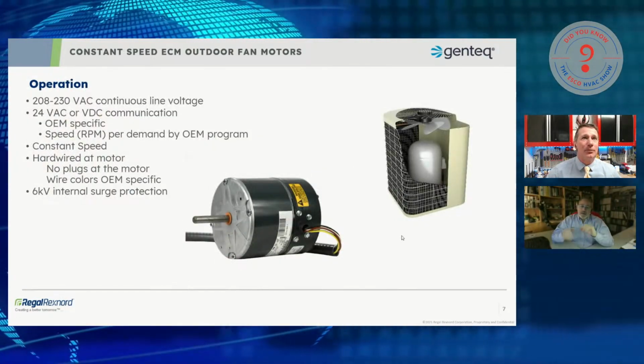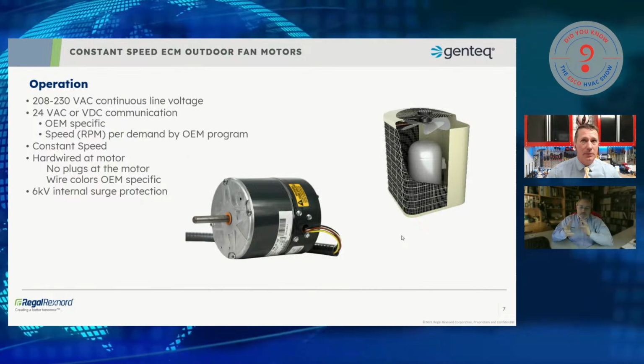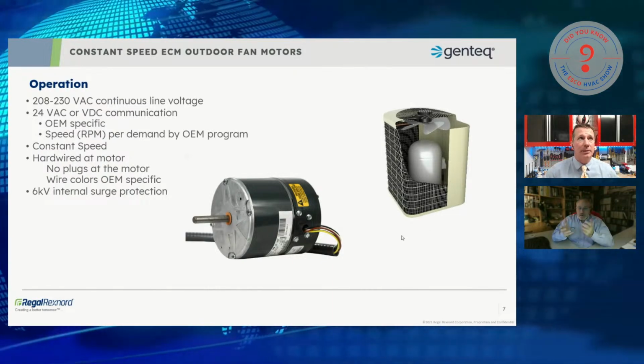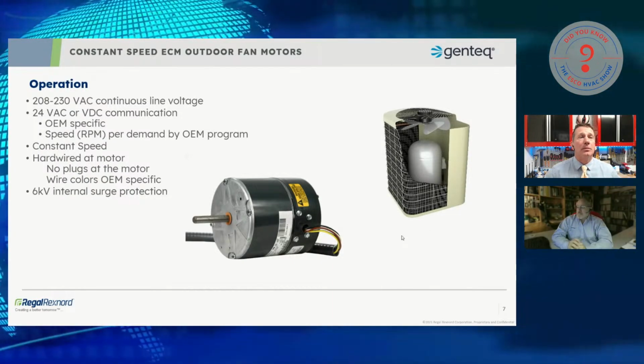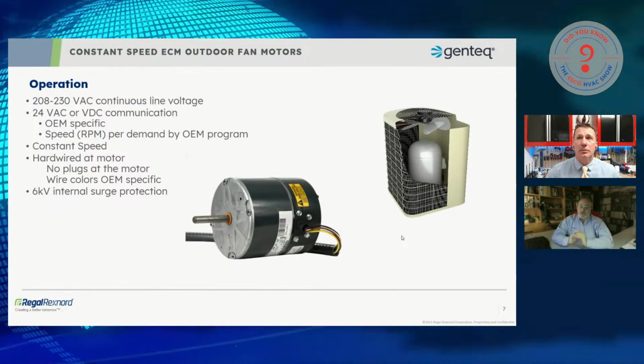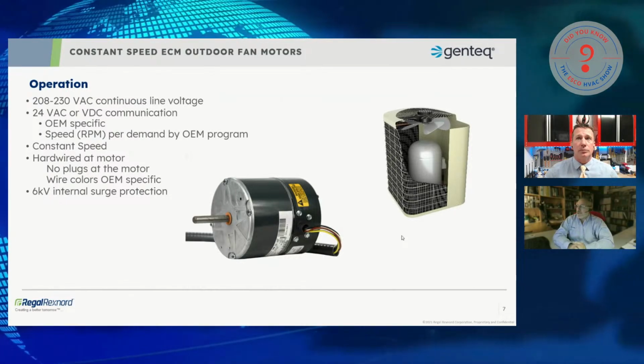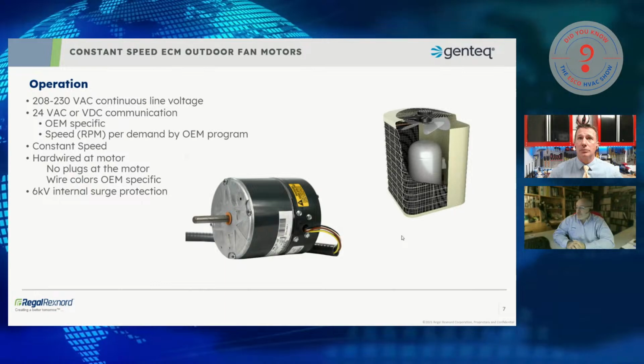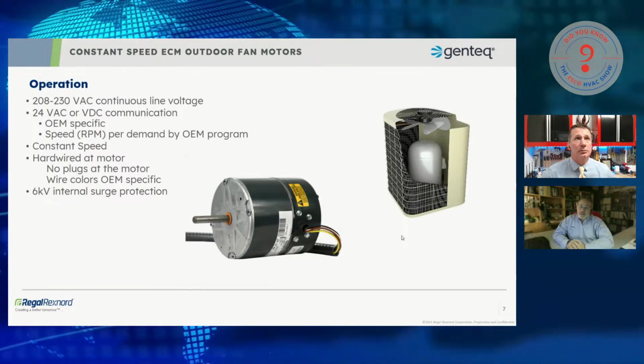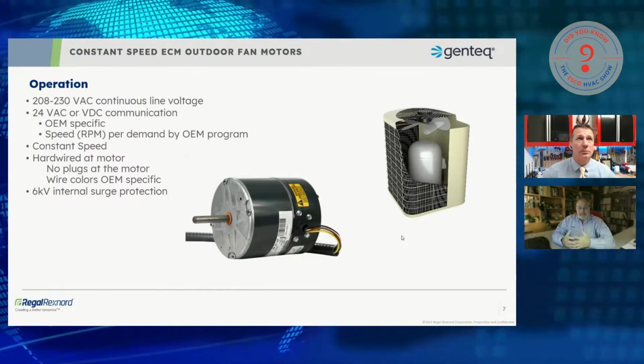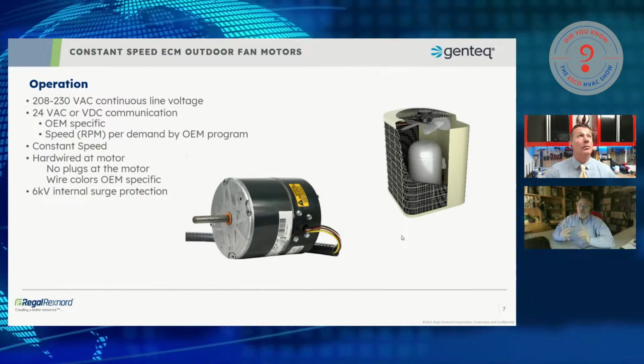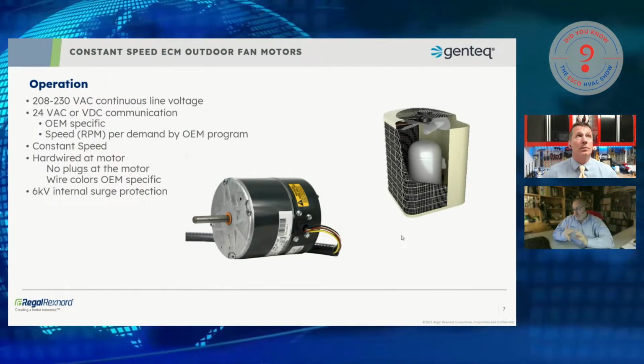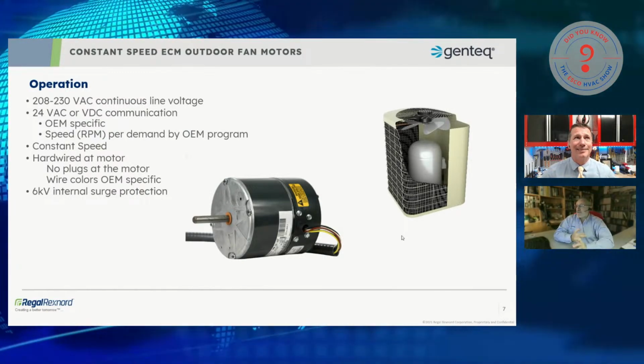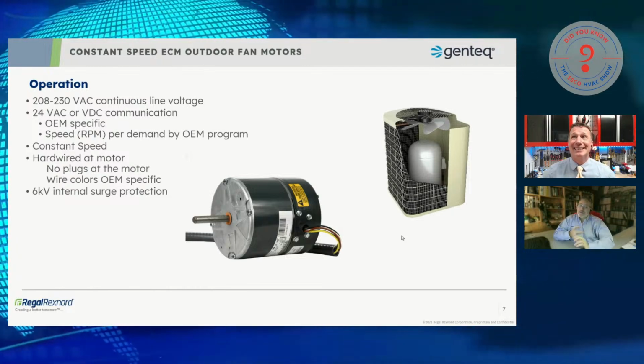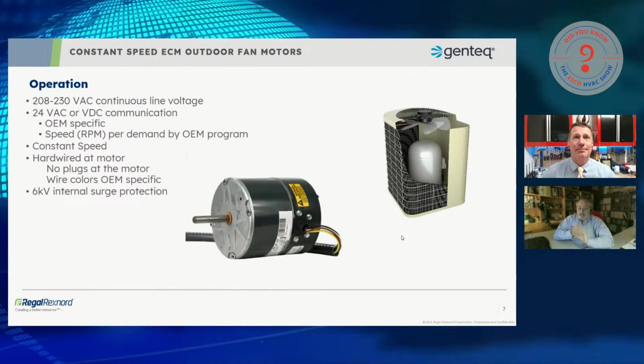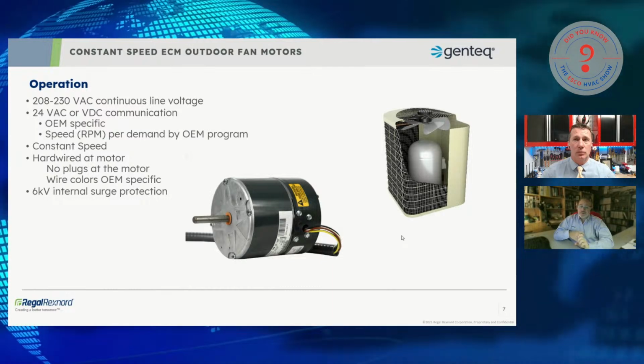So that's just a little bit of background on why you'll see this motor built in different orientations and what it looks like. The motors themselves, if we're talking strictly about residential like commercial applications, are typically built for 208, 230 volt. They could be operated or energized or commanded with either 24 volts AC or some form of DC voltage, which again, we'll take a deeper dive on very soon. That's OEM specific, and the RPM that it operates at, the speed that it operates at, is OEM specific.